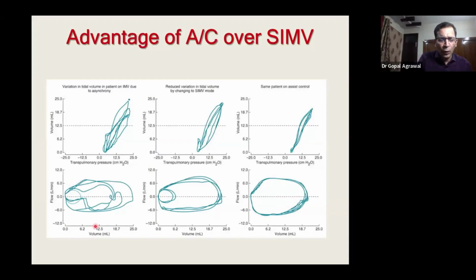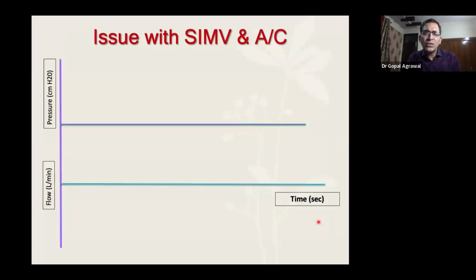Let's focus on this flow time volume curve. Here in IMV, there is complete asynchrony and heterogeneous breaths are being delivered across all the breaths. In SIMV, with supported breaths and unsupported breaths, there's better homogeneity compared to IMV, but the supported and unsupported breaths are heterogeneous. We can see the gross difference between both of them. But compared to SIMV, PTV mode or assist control mode has completely homogeneous breaths as all the breaths are supported equally. Just seeing this picture, you can see that assist control mode is a better ventilation mode compared to SIMV. So what is the issue with SIMV and assist control?